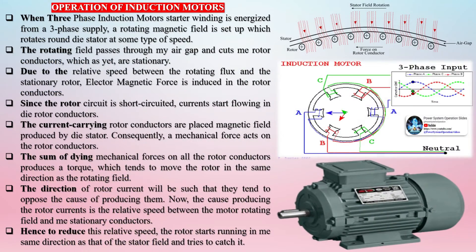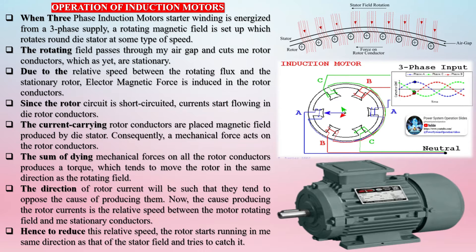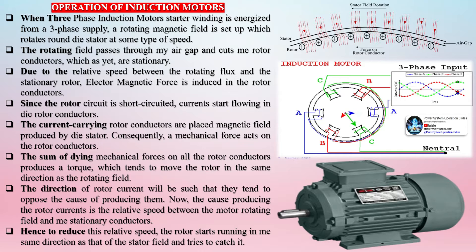When a three-phase induction motor's stator winding is energized from a three-phase supply, a rotating magnetic field is set up which rotates around the stator at synchronous speed. The rotating field passes through the air gap and cuts the rotor conductors, which are stationary. Due to the relative speed between the rotating flux and the stationary rotor, an electromagnetic force is induced in the rotor conductors. Since the rotor circuit is short-circuited, currents start flowing in the rotor conductors.